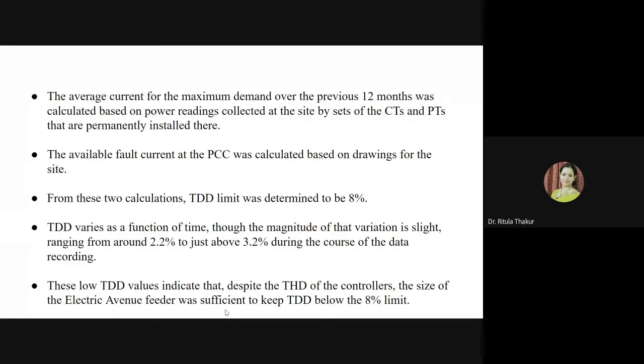And they observed that the low values of the TDD may indicate that despite the THD of the controller being very high, collectively, for Electric Avenue, the low value of the total demand distortion indicates that the size of the Electric Avenue feeder was sufficient to keep TDD below the 8% limit. So once we have become aware that these are the common problems created by charging stations, further studies and further designing of our feeder and equipment are to be done to keep the TDD below the 8% limit.